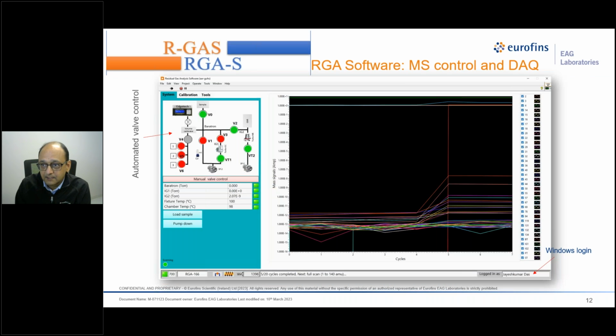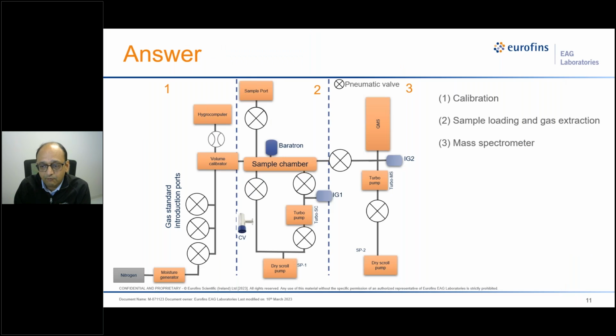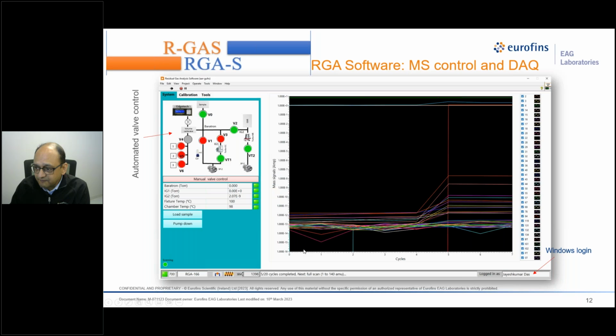So maybe I will go back here. Now, let's say I want to calibrate the mass spec for 5,000 ppm of moisture. So I would generate that 5,000 ppm plus nitrogen mix and introduce it to the mass spec. But before doing that, I have to make sure that my sample chamber background is acceptable and in the range of being used. So what we do, as you can see here, is the first 5 scans, so 0 to 4, are taken when these two valves are closed and V2 is open.